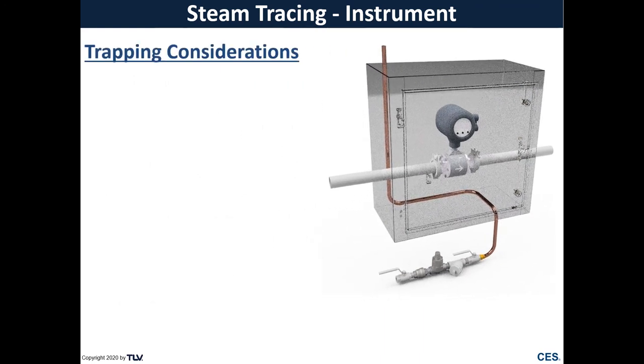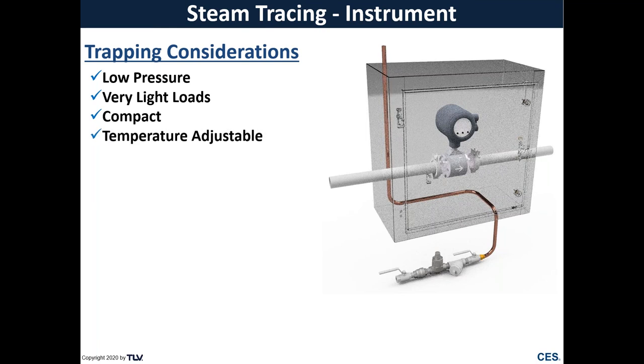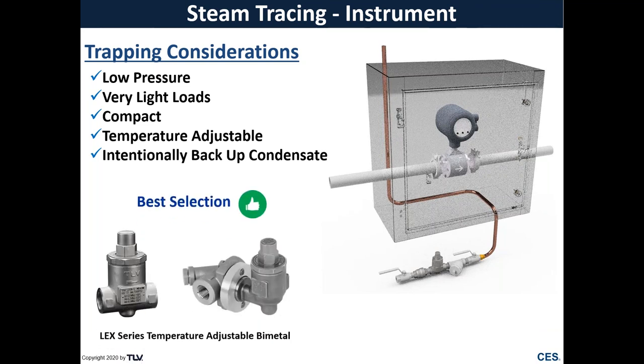So our trapping considerations here, generally they're low pressure, very light loads, and we're going to want something that is very compact and easy to install. And here we're going to want to take advantage of a temperature adjustable trap to actually intentionally back up condensate and use the sensible heat of that condensate to do the heating rather than the latent heat of steam. So this is a perfect application for something similar to our Lex series temperature adjustable bimetal trap.